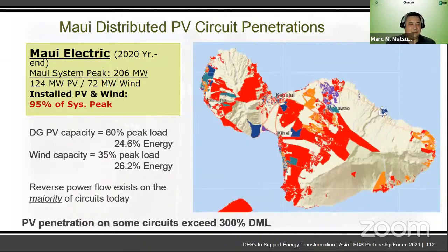The red lines you see here are distribution circuits that Hawaiian Electric has deemed to have maxed out on their penetration levels. A lot of them are filling up and backfeeding—we have circuits with three times the amount of connected solar than they have load during the daytime, so there's significant backfeed on some of them.